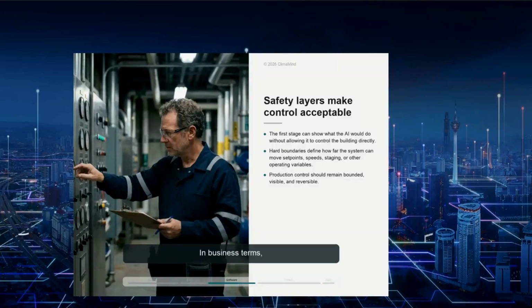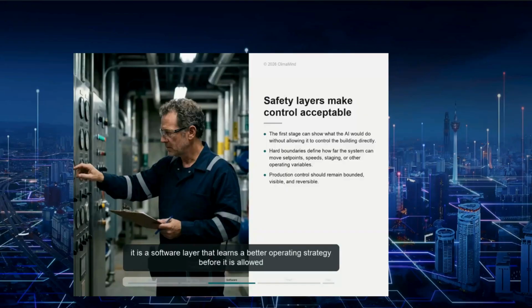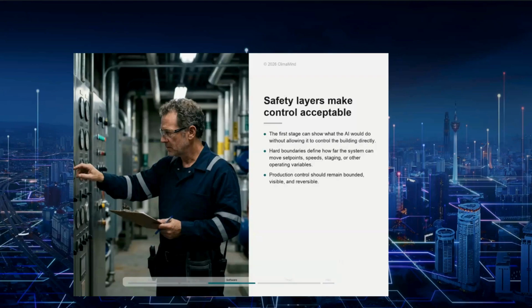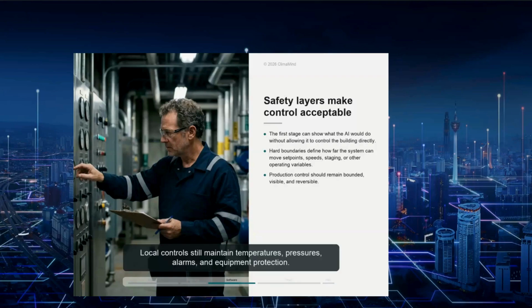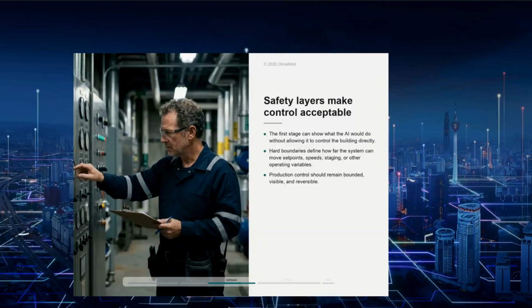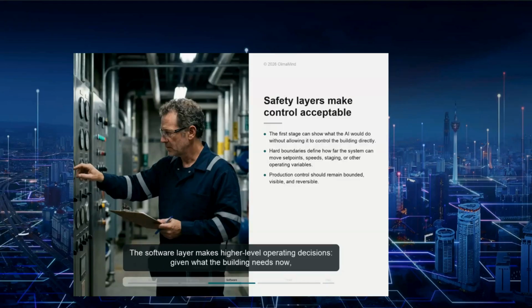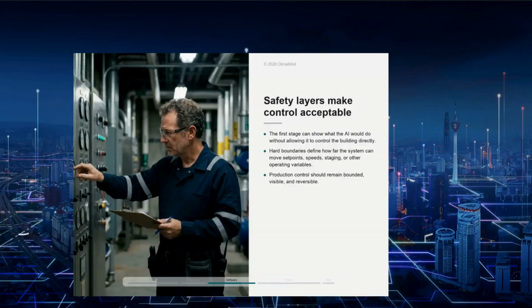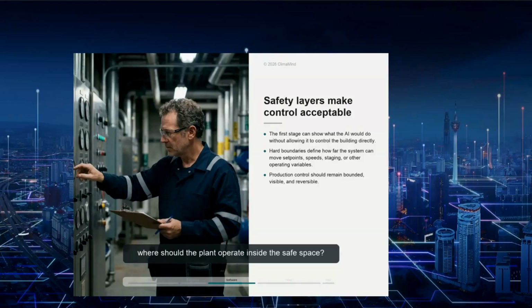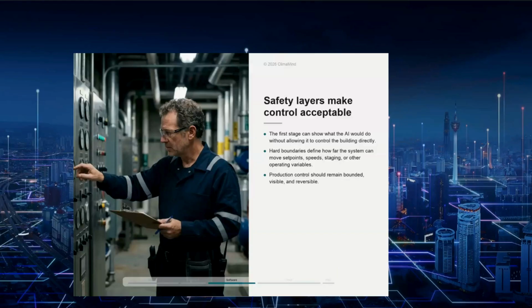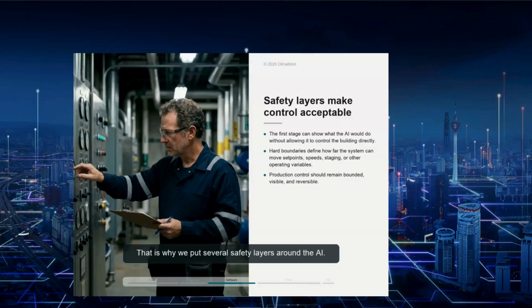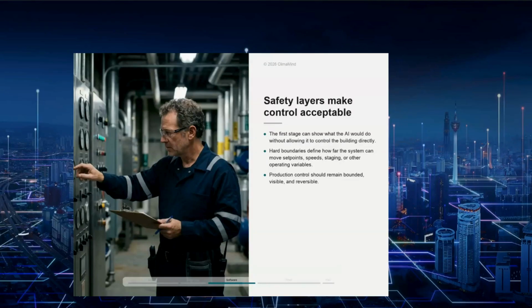In technical terms, this is reinforcement learning applied to HVAC control. In business terms, it is a software layer that learns a better operation strategy before it is allowed to control anything broadly. Local controls still maintain temperatures, pressures, alarms, and equipment protection. The software layer makes higher-level operation decisions. Given what the building needs now, where should the plant operate inside the safe space? That is why we put several safety layers around the AI.